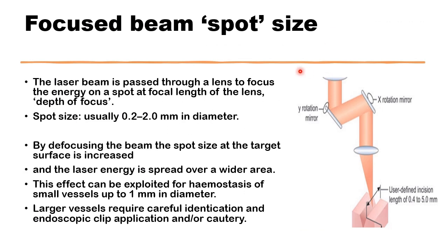The energy delivered by the laser machine needs to be focused in a spot in order to achieve the temperature required to ablate or cut into the tissue, and achieve this very quickly. Now this can be done through a lens in the end of the laser machine that focuses all the beam of the laser into a very tiny spot.